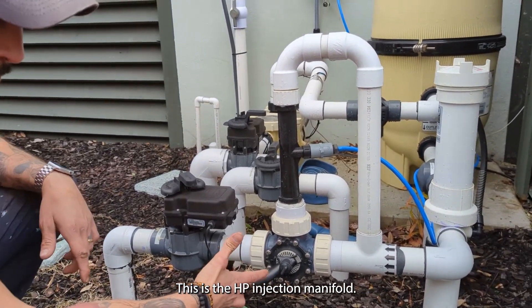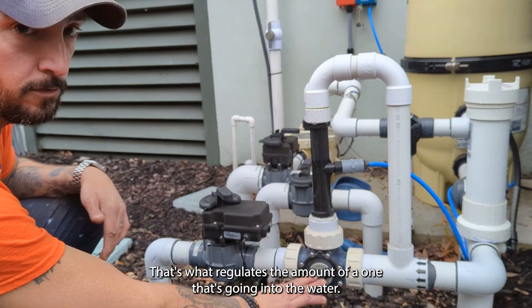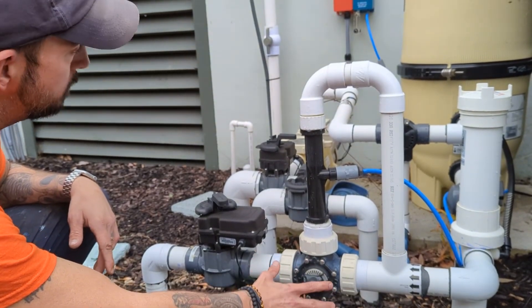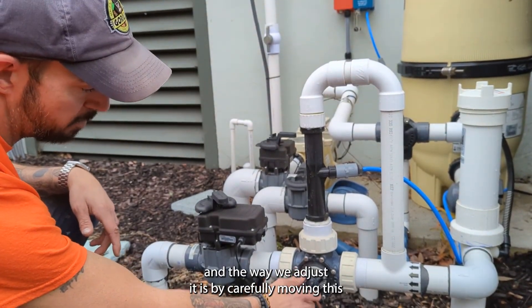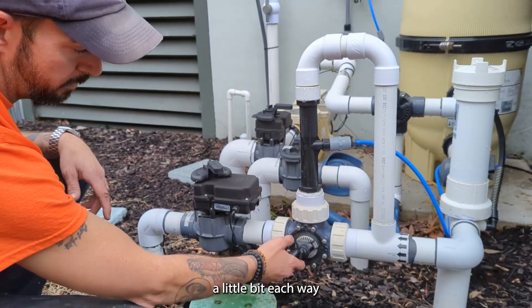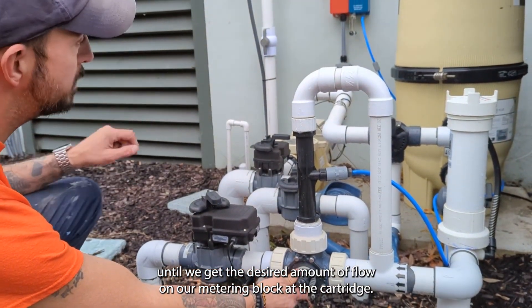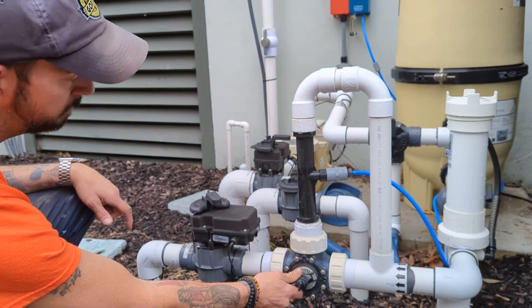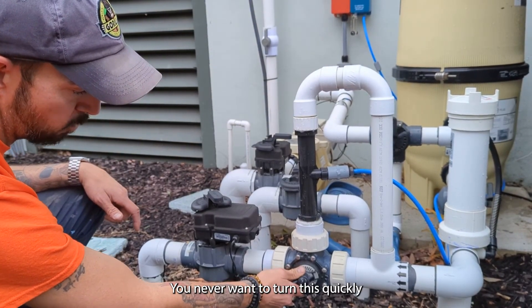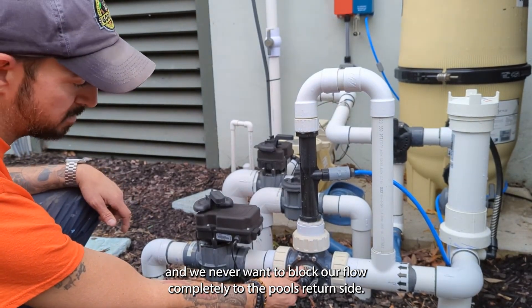This is the HP injection manifold — it's what regulates the amount of ozone that's going into the water. This valve handle controls that flow, and the way we adjust it is by carefully moving it a little bit each way until we get the desired amount of flow on our metering block at the cartridge. Move it in small increments and slowly. You never want to turn this quickly, and we never want to block off flow completely to the pool's return side.